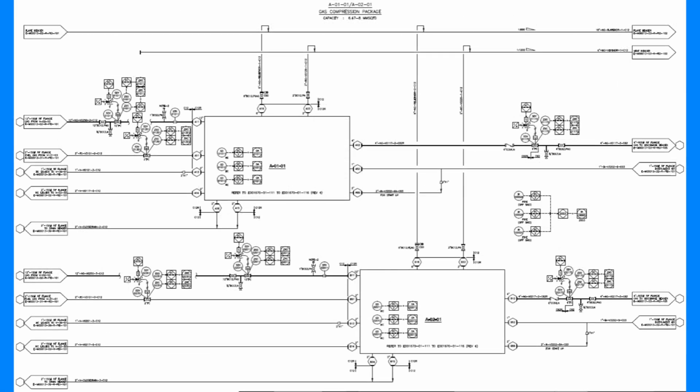What is a P&ID? A P&ID is a diagram which shows the interconnection of process equipment and the instrumentation used to control the process. In the process industry, a standard set of symbols is used to prepare drawings of processes. The instrument symbols used in these drawings are generally based on ANSI/ISA's S5.1-1984, R1992. In plain terms, a P&ID is a one-line schematic diagram using symbols to show piping, equipment, instrumentation, and interconnections between them.